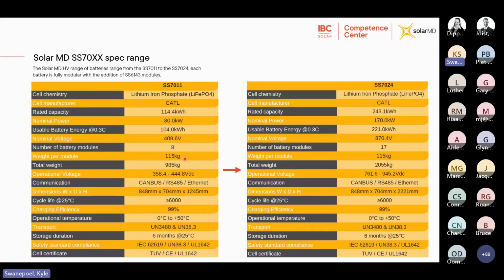The weight per module stays the same, it's 115 kilograms, and then the total of your 8 modules plus the frame plus the BMU will come in at 985 kilograms. These battery solutions are fully modular, so they are shipped in 115 kilogram battery packs based on the order. The frame is also flat packed and the BMU is boxed separately, so it is assembled on site. It makes it easy for installation as well as for maintenance. You don't need any special equipment. It can be done quite easily with just 2 people.